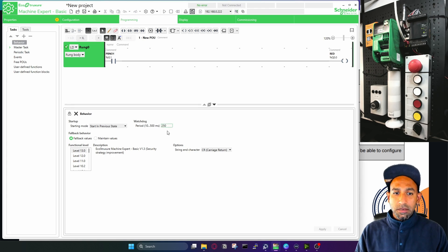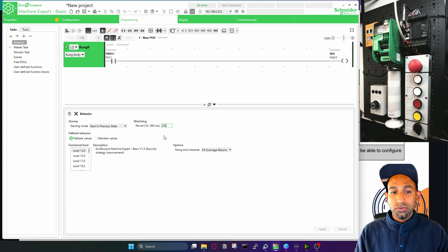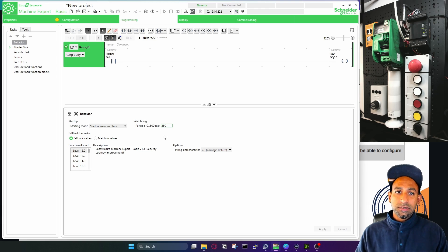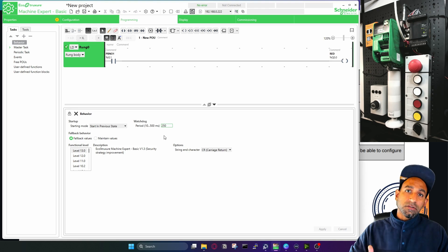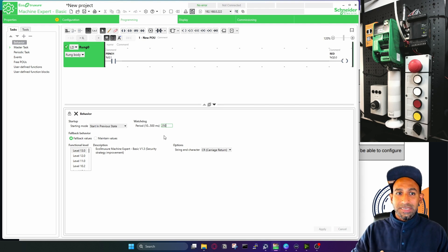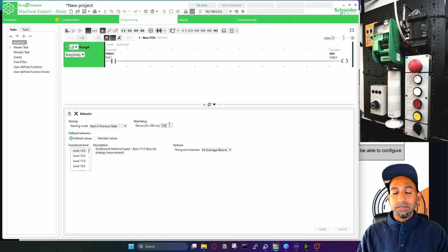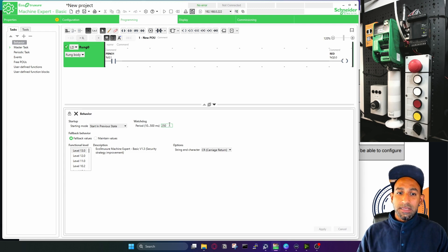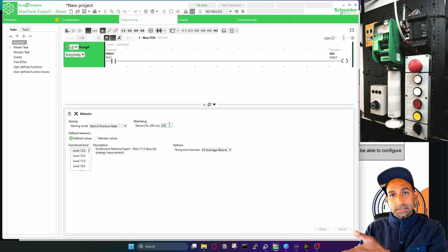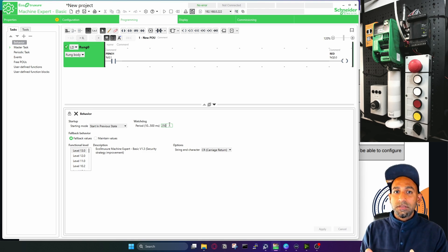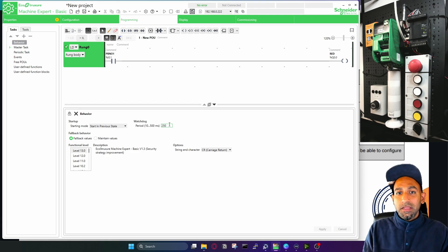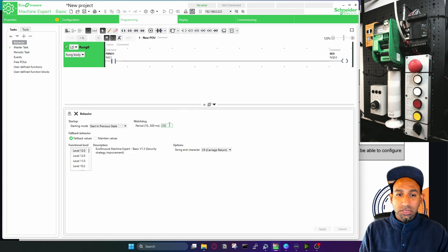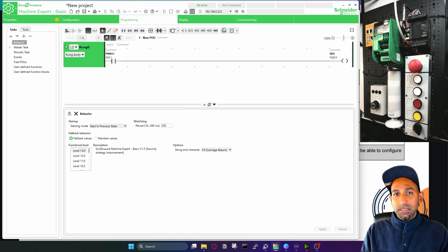Then you have the watchdog timer, which by default is set to 250 milliseconds. When you have a bigger program, the scan time depends on the length of the program. If you have multiple loops, the PLC needs more time to solve the logic. If the time exceeds the watchdog time, the PLC will raise an alarm or error state. This watchdog timer is the limit the PLC should not cross. You can also change this value if needed.